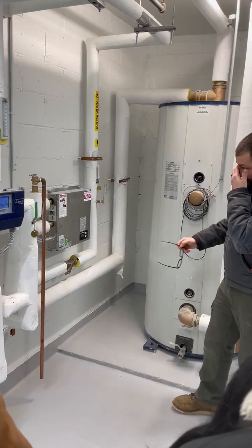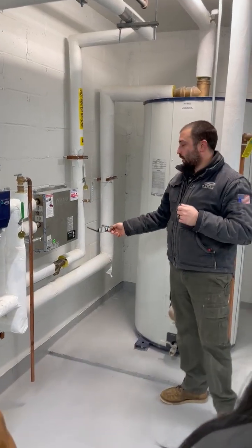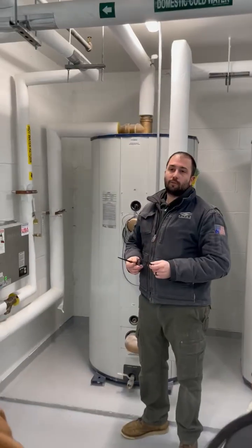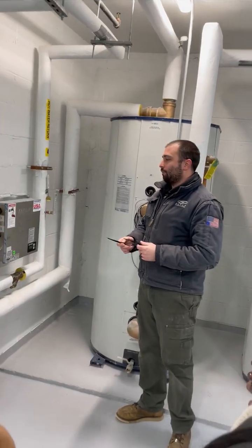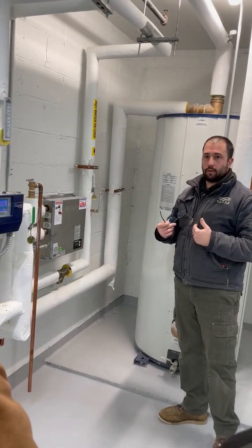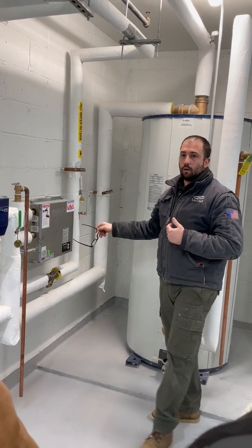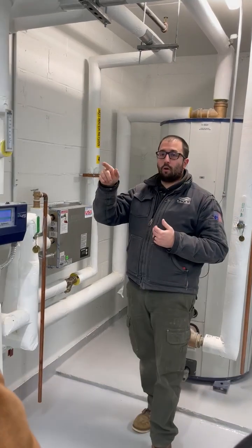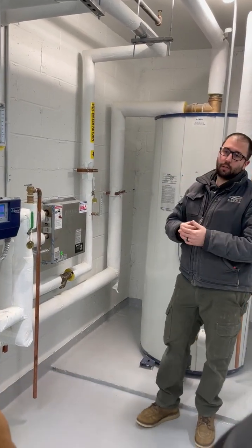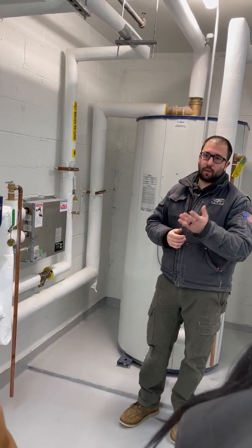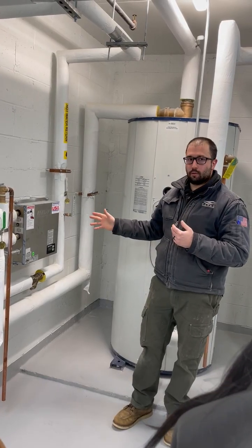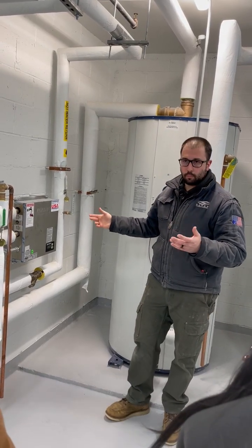As far as temperature, the code for return water is typically 110 to 115. I personally like setting it to 120, because the aquastat on the wall, which is controlling the pump - I'll show you guys in a little bit - is usually about 115. So that'll turn on and off. I give it about a 5-degree delta, so difference in temperature.